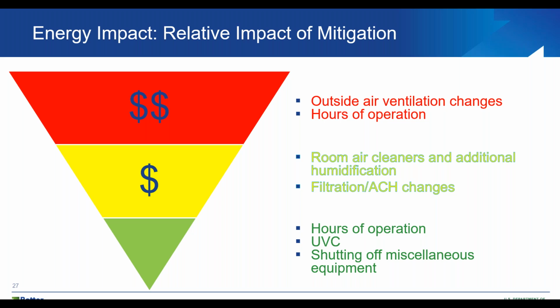It's hard to put a specific number on it. It's 10 to 20% more energy for the air handling unit. It's going to be more with a lot more outside air, and the same with the hours of operation. So if you're operating 10 hours a day, and then you go to 12 hours a day, you get a 20% increase just in the fan energy, potentially, and not including the heating or cooling. And if you're going 24 hours a day, you could double the amount of fan energy from going from 12 to 24. If they're constant volume. If they're VAV and they're modified, not as much, but you'll still notice it.